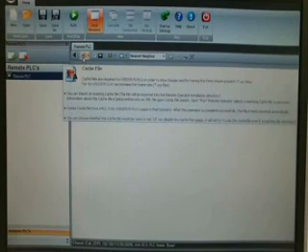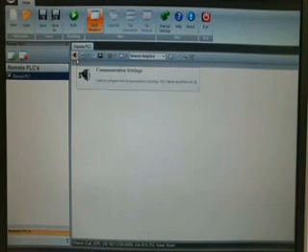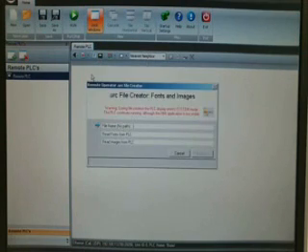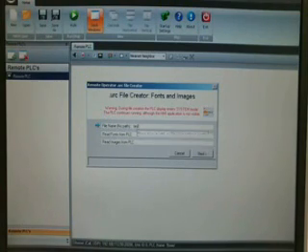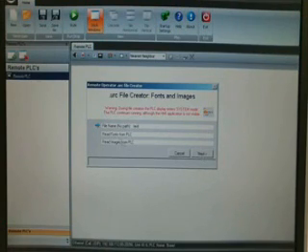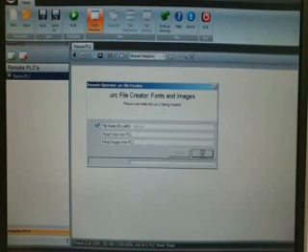Once we have that set up, if you notice when we were looking at the PLC, there were some graphics. In order for a remote operator to show those graphic files, we need to create a cache file. So next to the communication settings icon is a cache file icon. And we're going to go ahead and create a cache file. Which in order to do that, we need to go ahead and set a file name. And I'll just type in a name for now, which is test. Once you have a file name, hit the next button. And if you can communicate with the PLC, it's going to go out. The remote operator will go out and check and grab whatever graphics are involved with that PLC.